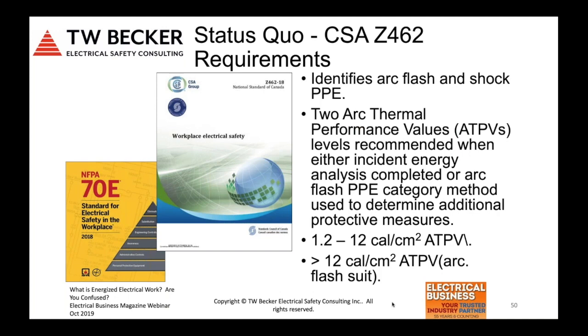So again, arc flash and shock PPE, there is no other standard that I'm aware of that has the detail and content on electrical specific PPE tools and equipment other than 70E and Z462. Remember, technically harmonized Z462 is based on 70E with a Canadian slant in its format and referencing other Canadian standards. So really at the end of the day, 2 choices for arc rated clothing: an everyday wear shirt and pant or coverall, which is now identified against incident energy as 1.2 to 12 calories. The second choice would be greater than 12 calories, which would put you into an arc flash suit. So again, single layer shirt and pant or single layer coverall, arc rated face shield, balaclava, canal insert earplugs, CSA approved safety eyewear, approved safety footwear, and then for the arc flash suit, again, bib overall, jacket, and arc flash suit hood.